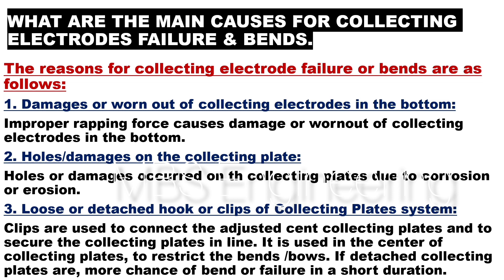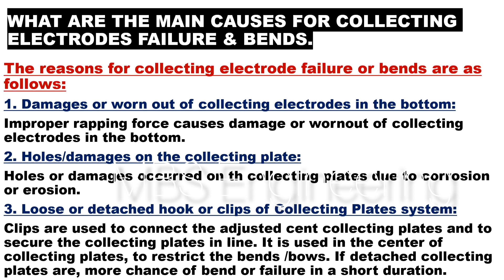One of the causes for collecting plates bends is loose or detached hooks or clips of the collecting plates system. Clips are used to connect the adjacent collecting plates and to secure the collecting plates in line. They are used in the center of collecting plates to restrict bends and bows. If detached, collecting plates have a greater chance of bend or failure in a short duration.